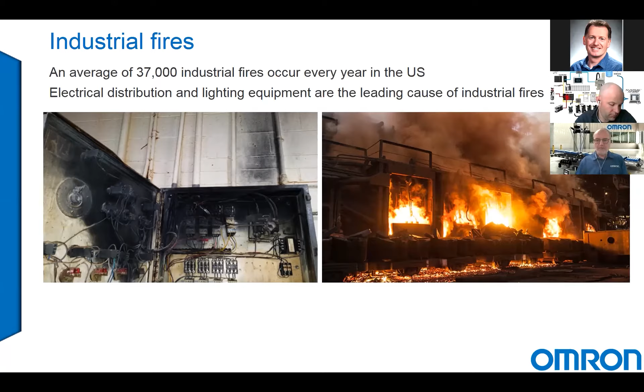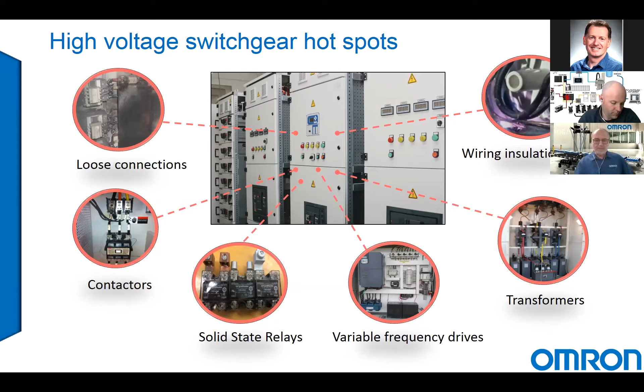To prevent that, here are different pictures of situations where you have a loose connection that heats up, and the connector block will finally melt or catch fire. We have also contactors that can be the source of a fire. Solid state relays, if they're overheating, can explode and catch fire. Variable frequency drives, transformers, and whatnot.